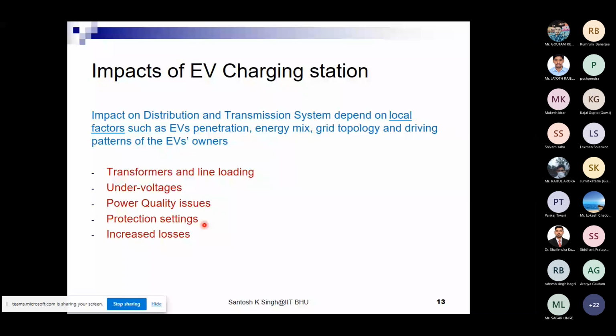But if we are bringing down these charges, then they can start affecting the protection setting, because the wrong signal is going to give a wrong impression that some fault is happening, when actually it is coming from a spurious harmonic signal. So those losses will be there because of the harmonics which are present.